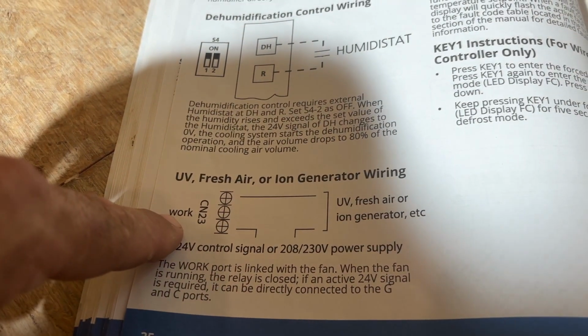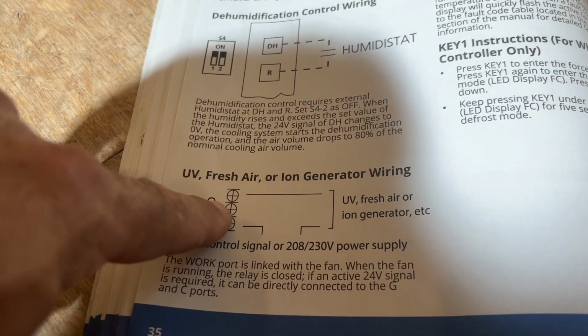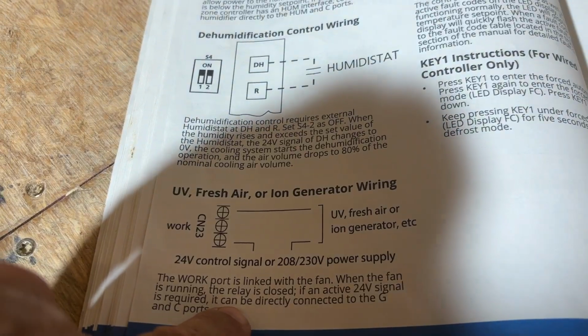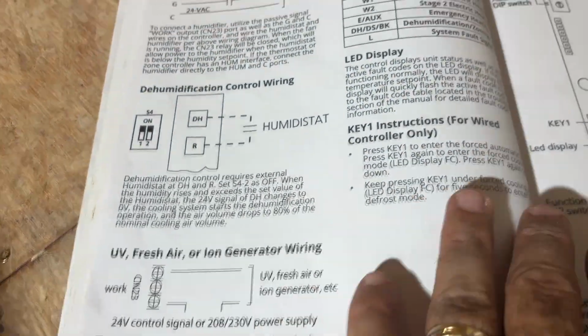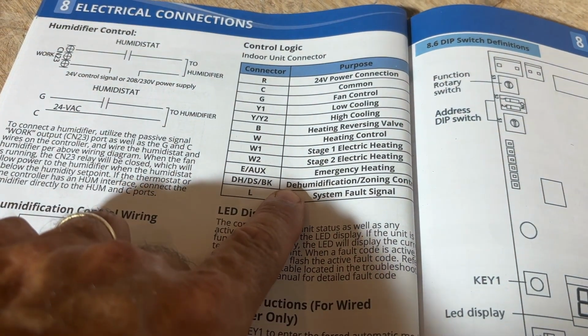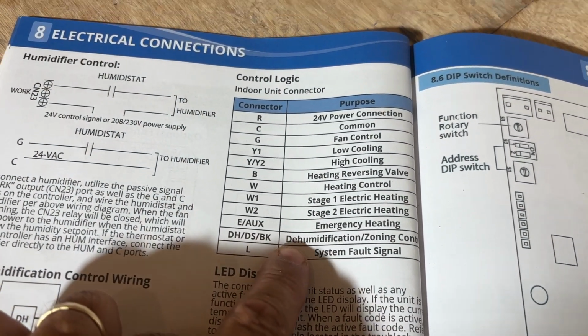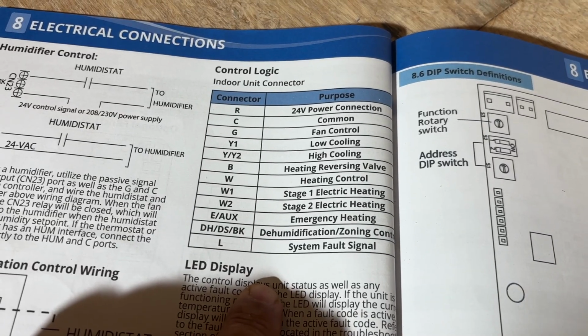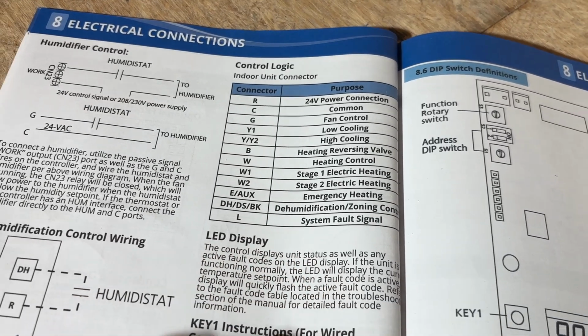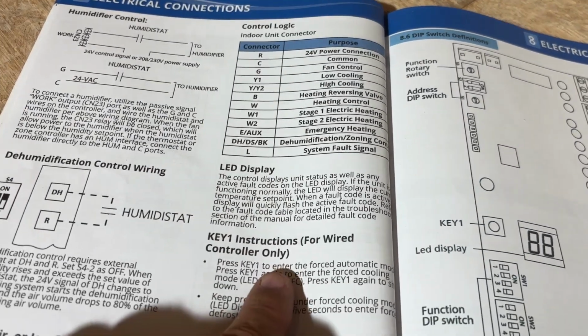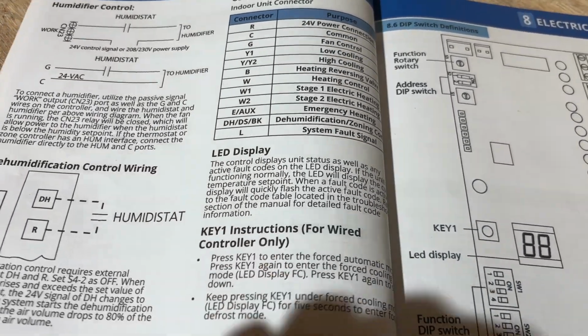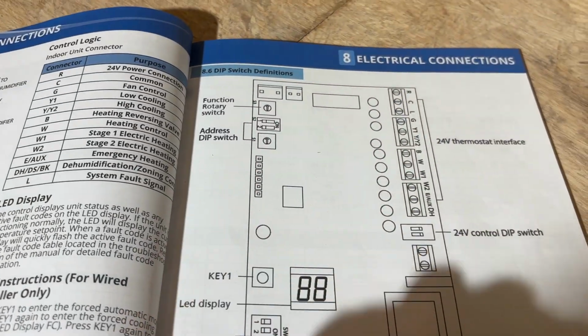The UV fresh air ion generator wiring, we are going to do that. We have an ERV that we're going to hook in for fresh air that hooks in with the fan work port, so we will look at that later. And then you have your control logic. So all of the labels here on the circuit board. What the manual doesn't do is really get into exactly what those specific things do. LED display, an overview of your circuit board.